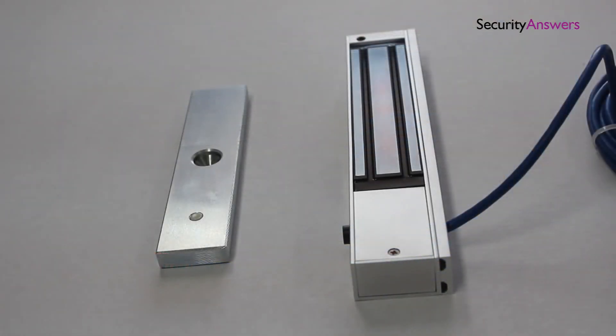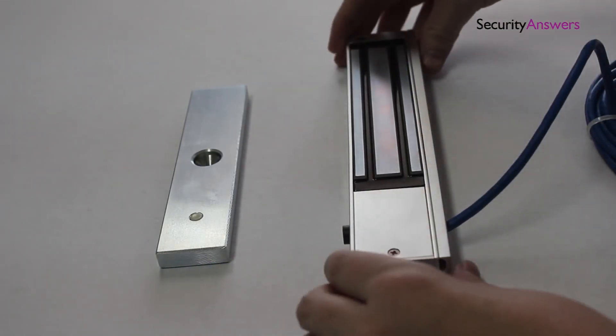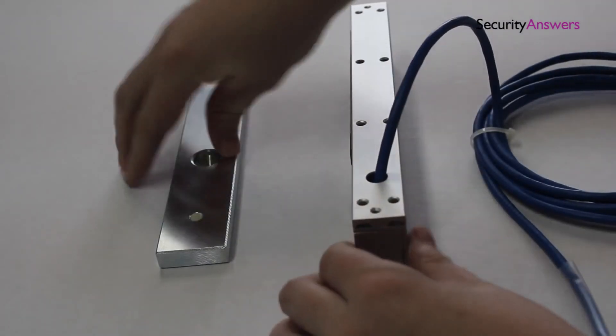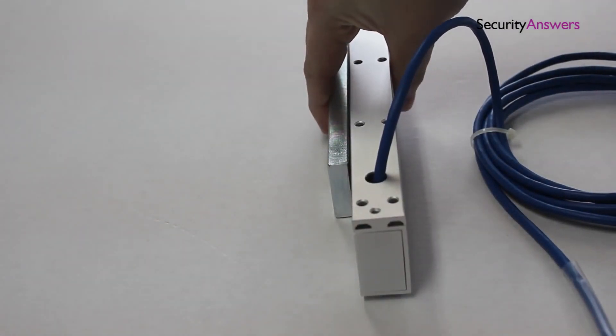In order for an EM lock to function, it's extremely important that a thorough connection is made between the two magnets. So take extra care when marking off the area for the second device to guarantee correct alignment.